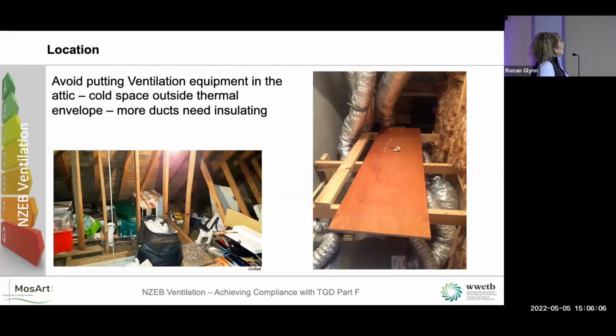So again, where am I going to put my ventilation system? So we say avoid putting your ventilation equipment up in the attic. If you're anything like me, you probably go up in the attic once a year to get the Christmas decorations and shove them back up there, which looks like what's happening here. The ventilation system is buried in here at the back, as you can see, not getting the love and care that it deserves. At the end of the day, it's our lungs, so we need to be looking after it. You can see here on the right-hand side, the ventilation system is actually underneath that piece of timber, and we can't see what's going on at all. If you have it upstairs or up in the attic in that cold area, you have to insulate all of your ducts. So we're saying they're not a great idea.